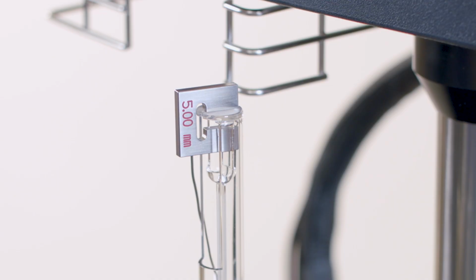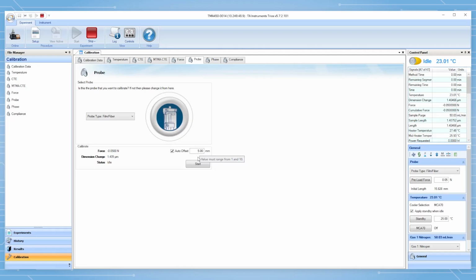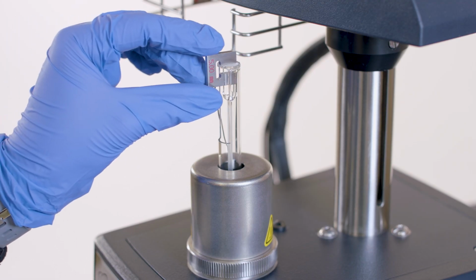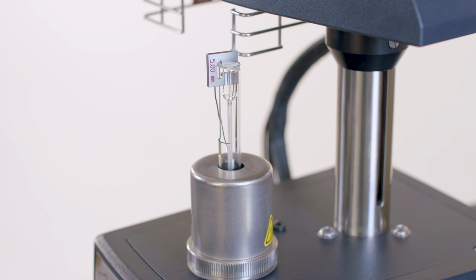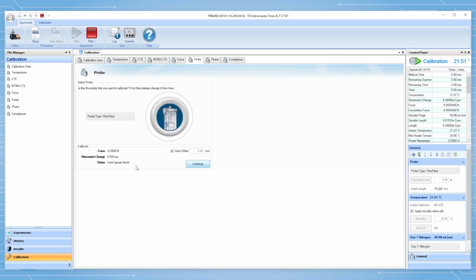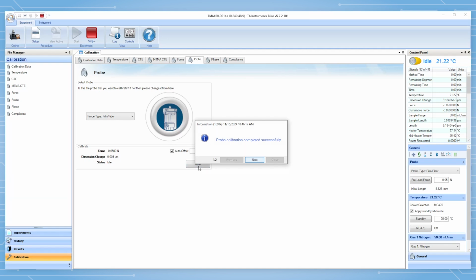Before you begin, you will need the 5mm gauge block. This is provided in your calibration kit. Start the probe calibration as usual. When prompted, you will need to insert the 5mm gauge block. With auto offset selected, Trios will automatically calculate the offset to compensate for the thickness and apply a calibration factor. This calibration will apply to any future length measurements while using the film fiber probe. Once calibrated, the auto offset does not need to be changed unless you reset the instrument parameters or use a new probe and stage assembly.